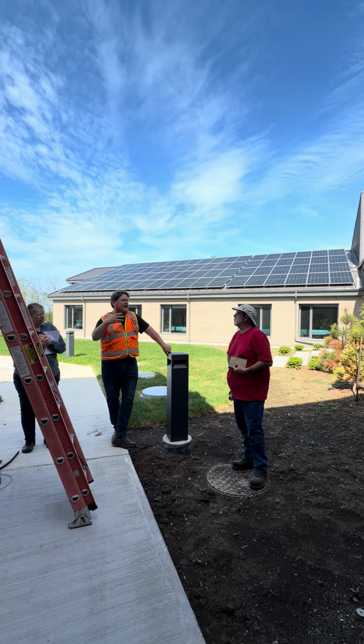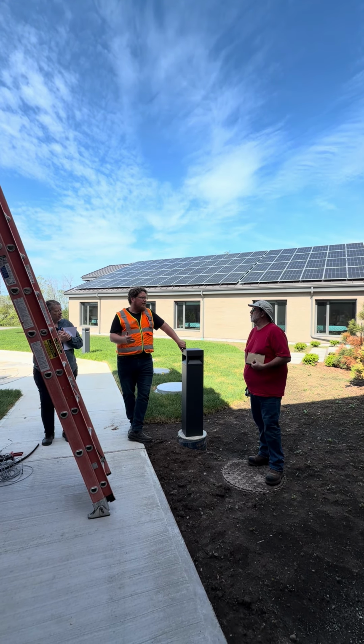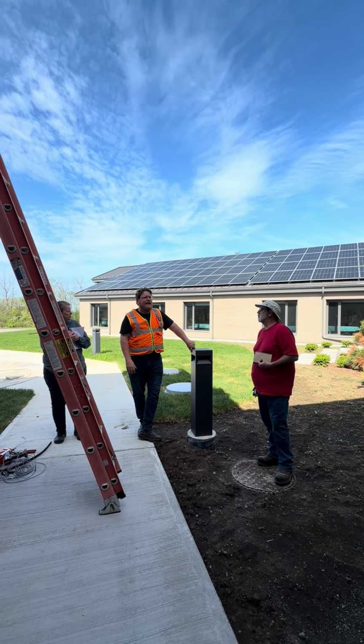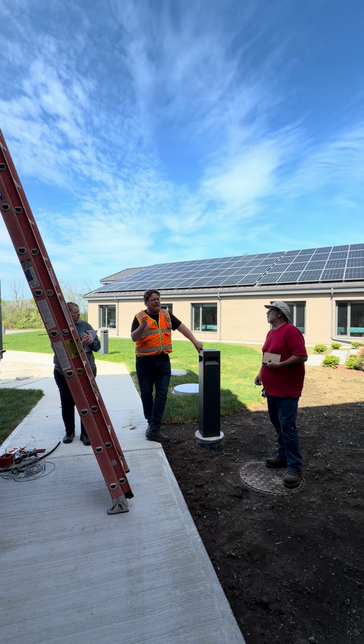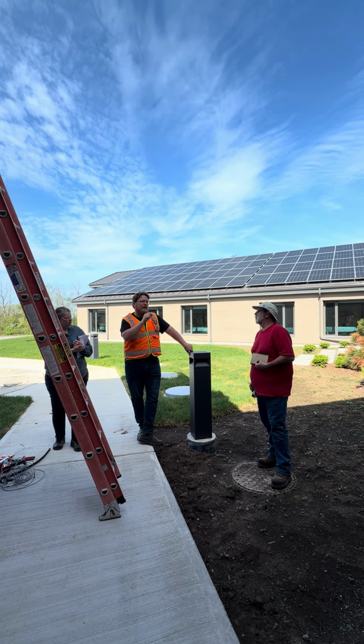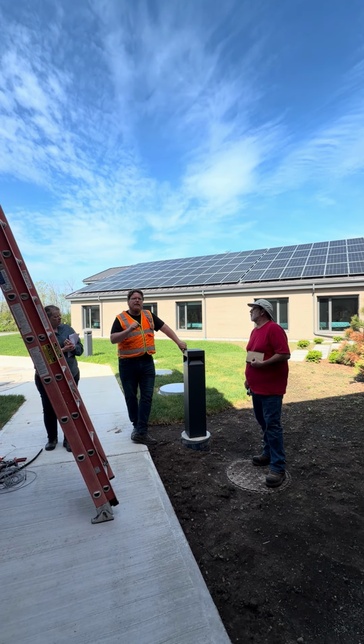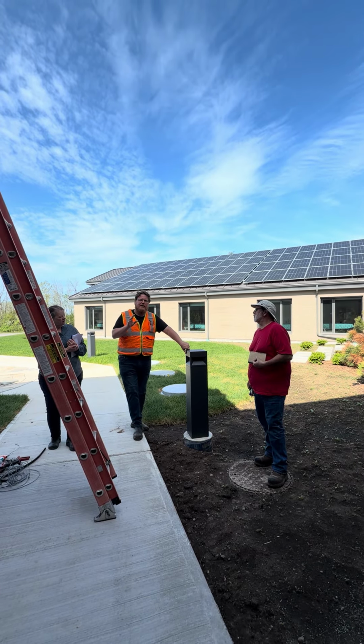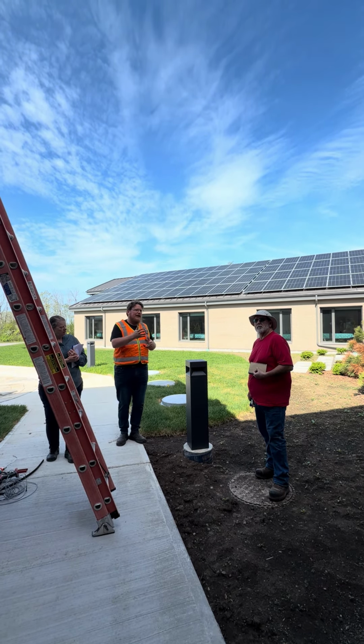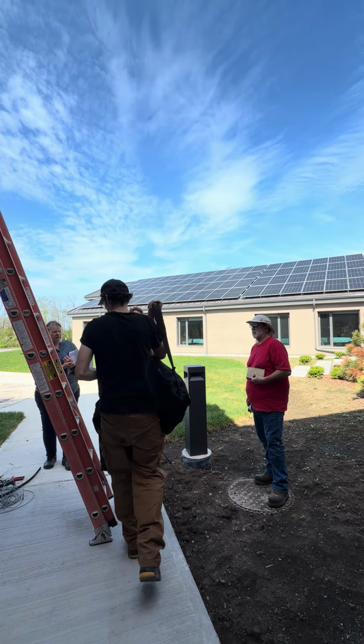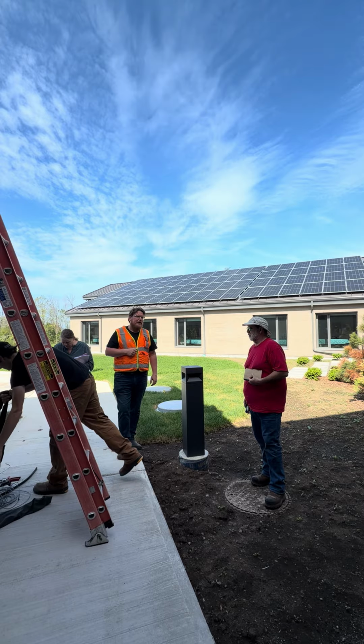But generally, once you get into operation, sometimes they pop up, sometimes they pop off. Some of it's a communications issue with the devices, since they're communicating along the power wire up there. So if you see it trip out, it doesn't automatically mean it's a problem. It might come back the next day, but if it persists, then that's when you look to do something about it.